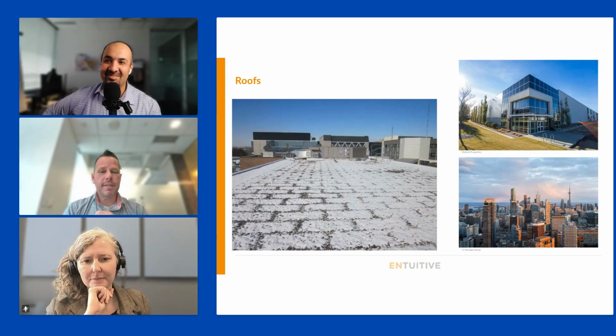So on the left, this is a photo I took, this might have been in Southwest Ontario. Really interesting example of thermal bridging occurring through an inverted roof system.